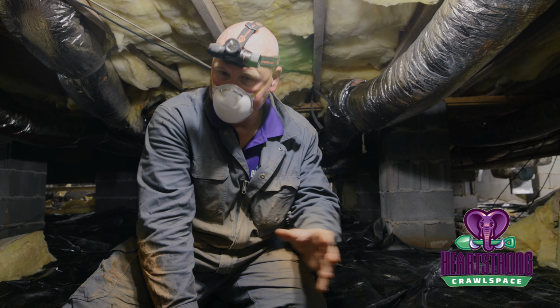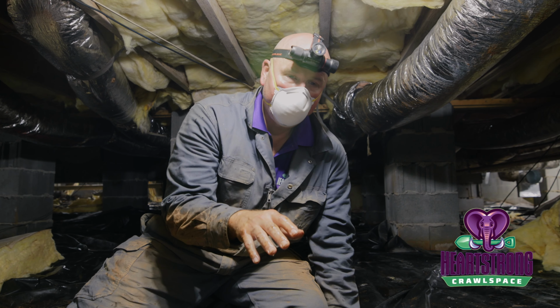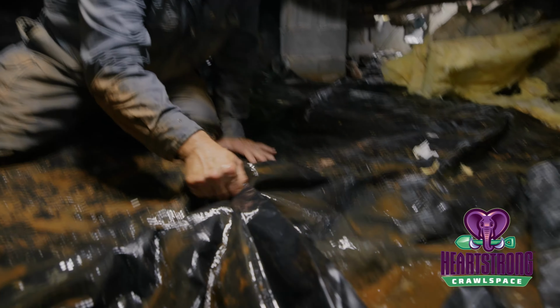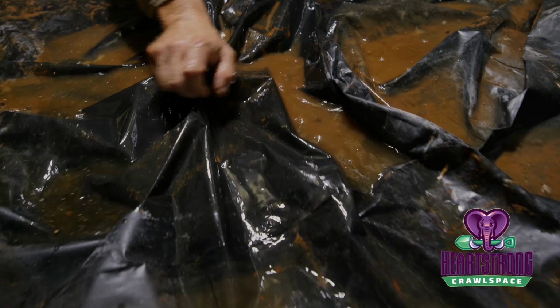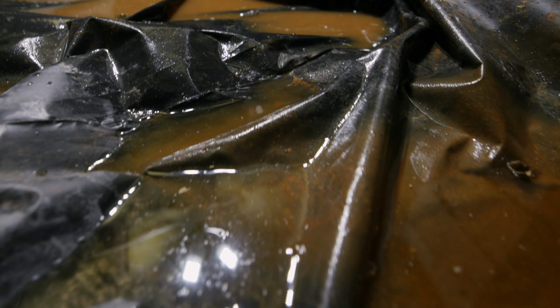things we notice. We see this, people say, oh, there's standing water inside of my crawl space. Is this caused by a plumbing leak? What's causing this? This time of the year, you can literally have this much water standing on top of the plastic because of the condensation. All of this just coming from the HVAC ductwork inside the crawl space. And it gets even worse in other areas, but that's what's causing that water to stand on top of the plastic today.